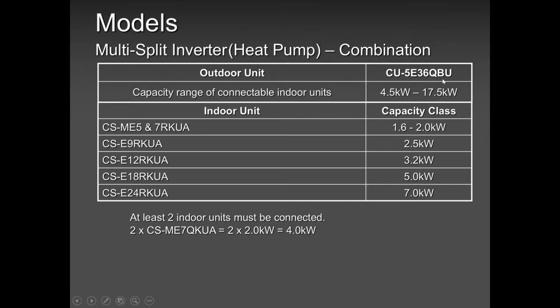This is a 5-zone. A 3-zone, a 4-zone, and a 2-zone are different. So this is an example, and this example has to be followed the same way on other multi-zone models. Now, if this was installed on a 2-zone, you would be good. On a 3-zone, you would be good, because the minimum and maximum is different on a 2-zone, 3-zone, and 4-zone. Okay, guys. But for this case here, for a 5-zone, we are different.